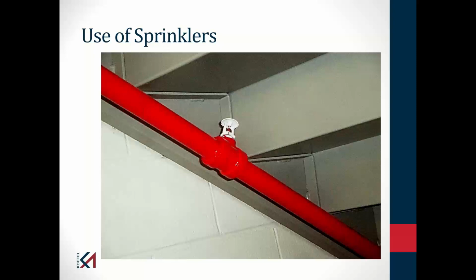Now, another thing that NFPA 25 addresses is what types of sprinklers may I use, or what types of sprinklers must I use in some cases in certain spaces. So going back to my light hazard occupancy, NFPA 13 now requires all new systems in a light hazard occupancy need to use fast response sprinklers. And I emphasize the word new. If you are rehabbing an existing light hazard space and it's still staying as light hazard, and it is protected with standard response sprinklers, then that would be acceptable. You can continue to use the standard response sprinklers. But if it's not a sprinklered space and you're putting sprinklers in, NFPA 13 will tell you that you need to use a fast response sprinkler.